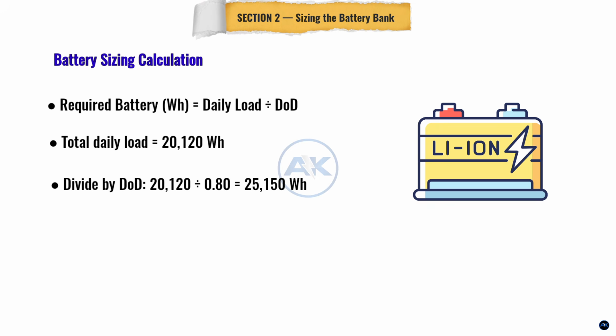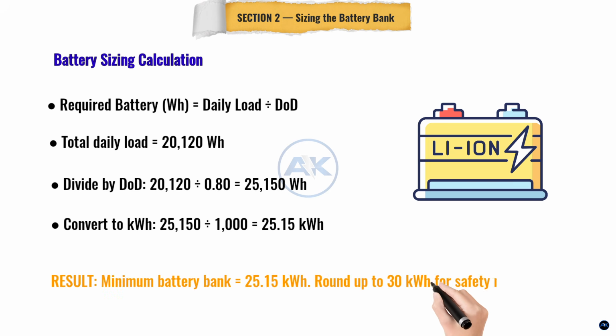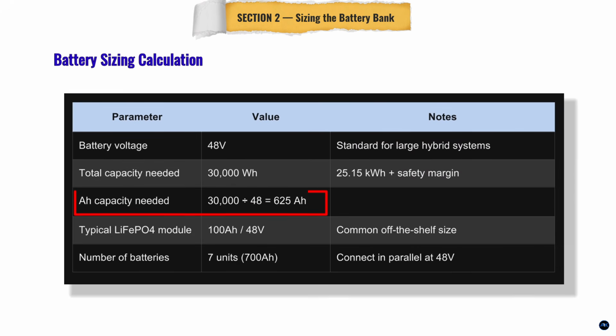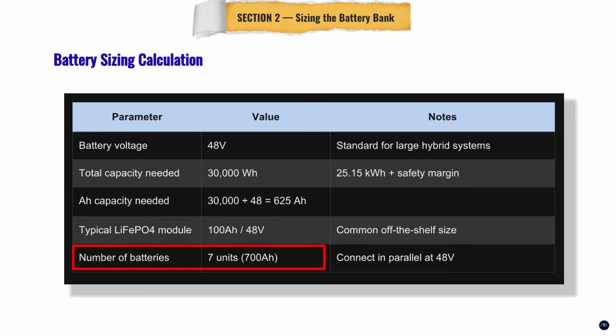Here is the battery sizing formula. Take your daily load, 20,120 watt-hours, and divide by the depth of discharge, 0.80. 20,120 divided by 0.80 equals 25,150 watt-hours. That is 25.15 kilowatt-hours of battery capacity needed. We always add a safety buffer, so we round up to 30 kilowatt-hours. At 48 volts, that means we need 625 amp-hours minimum. Using standard 100 amp-hour batteries, that is 7 batteries connected in parallel.